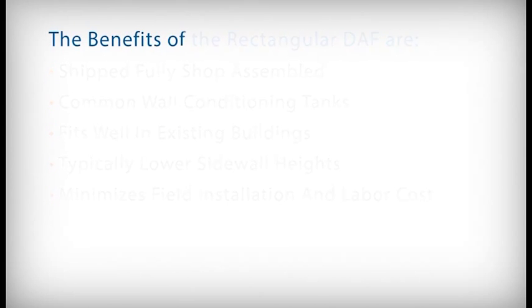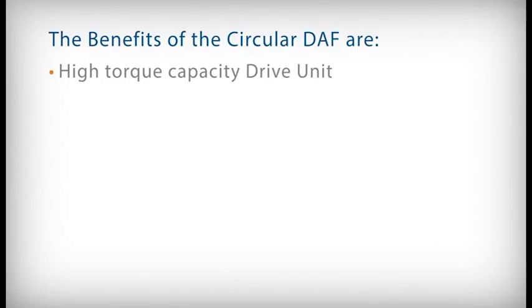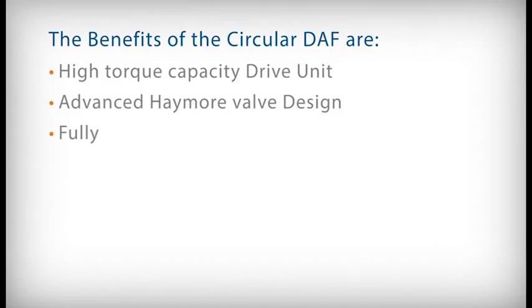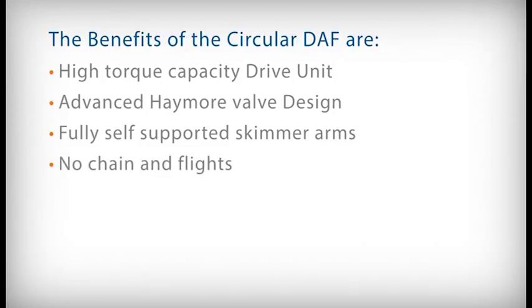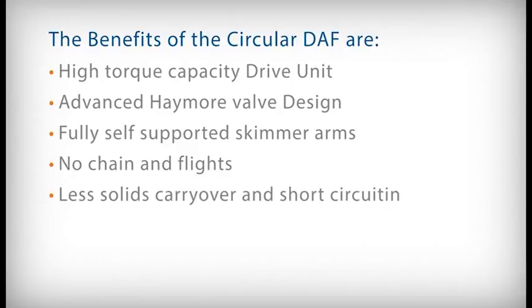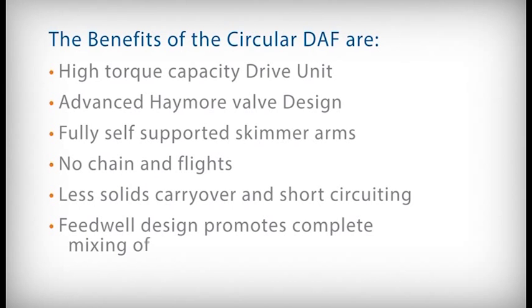The benefits of the circular DAF are a high torque capacity drive unit resulting in improved solids removal, the advanced Haymore valve design which allows delayed release of back pressure ensuring optimal bubble size, fully self-supported skimmer arms, minimal maintenance due to no chain and flights, less potential for solids carryover and short circuiting, and a feed well design that promotes complete mixing of influent.